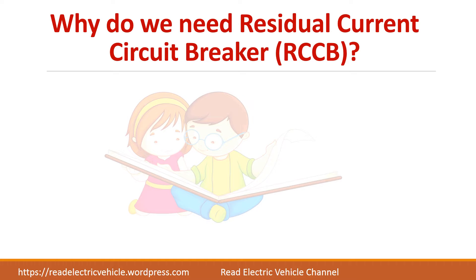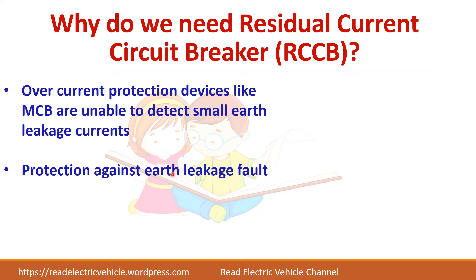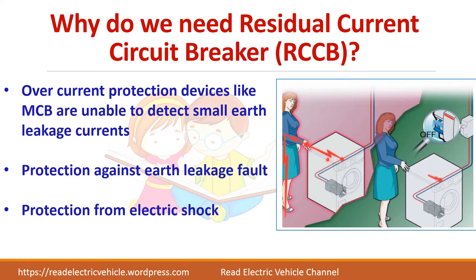Why do we need a residual current circuit breaker? We already use MCBs for overcurrent protection — whenever there is a fault, MCBs are good enough to isolate the circuit. But the problem with MCBs is that they are unable to detect small earth leakage current. To protect against earth leakage current, you have to use an RCCB. The main advantage is that it protects us from electrical shock.